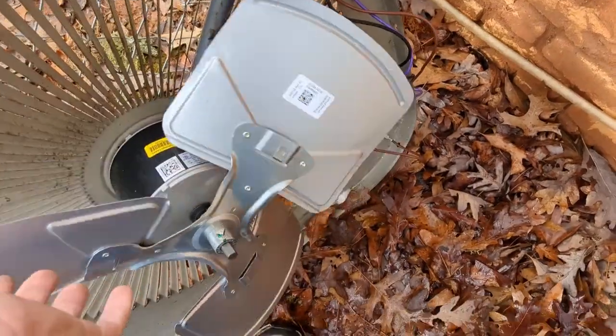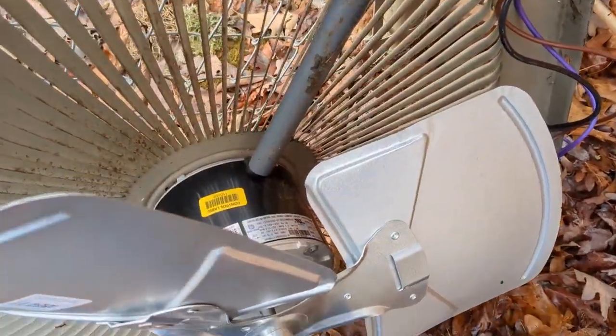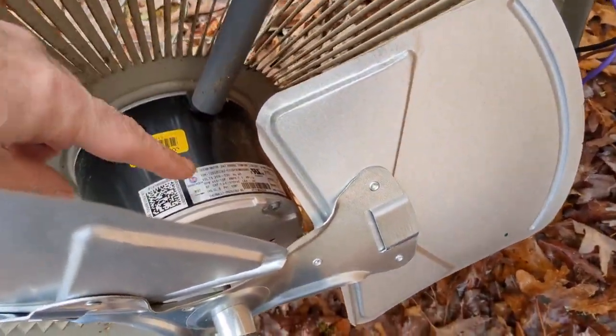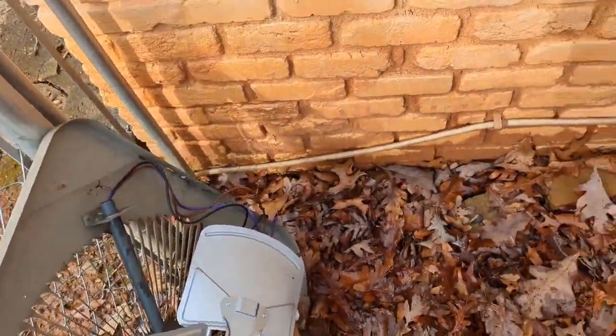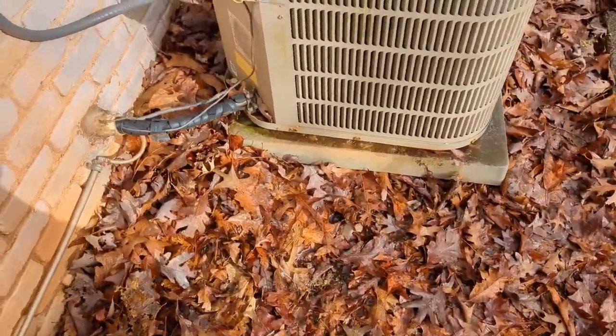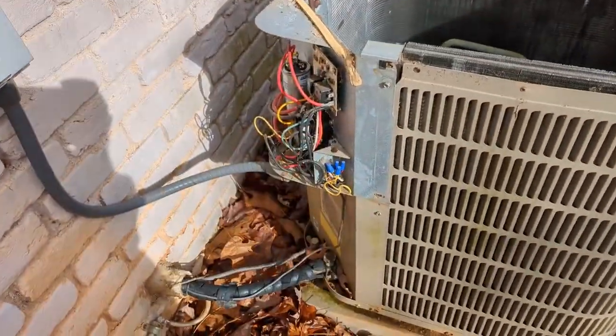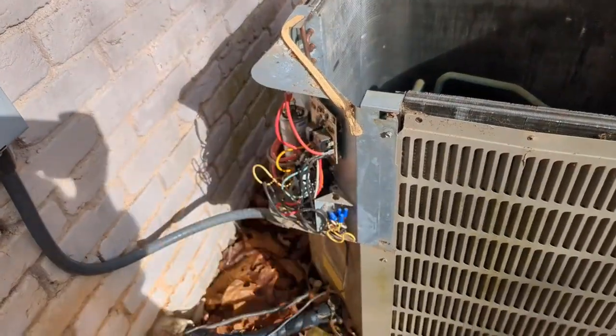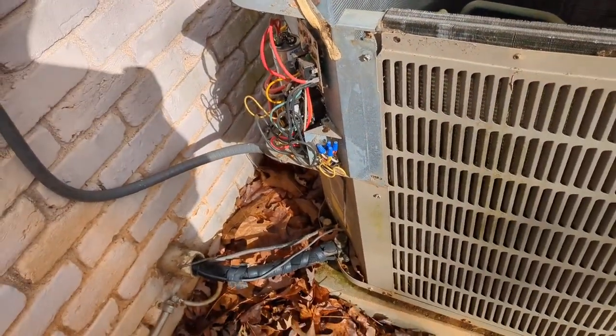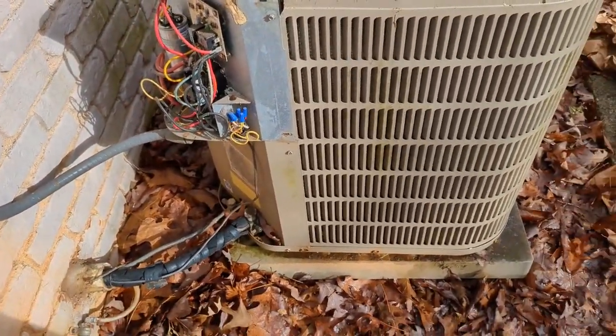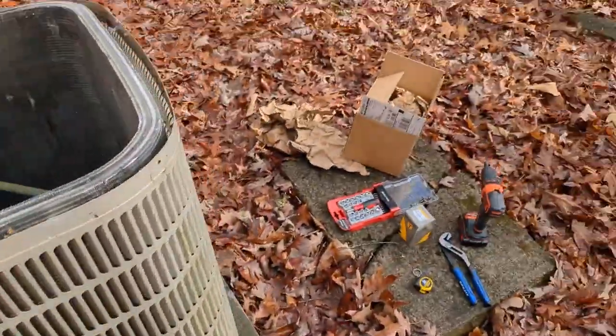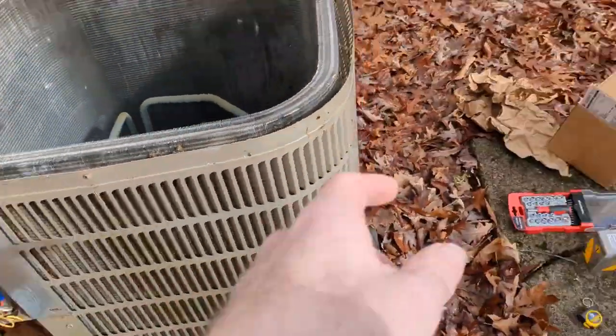It's close because the motor's been discontinued, so I had to get a sub. This one has 810, I think the original is 815, but the horsepower is exactly the same. Everything else matches up. Now, the service manual says this thing is supposed to have a 45 in it. Someone put in a 45.5, probably something grabbed off the truck, and 45 was close enough. But it's supposed to have a 45, and that's what I ordered.